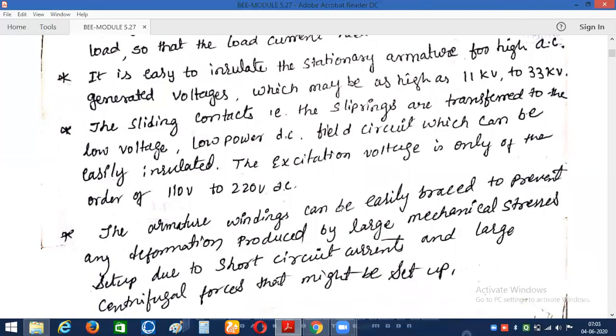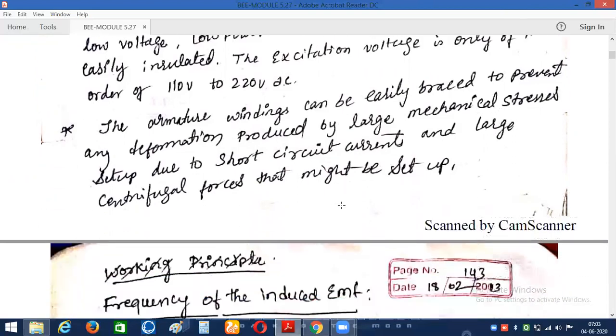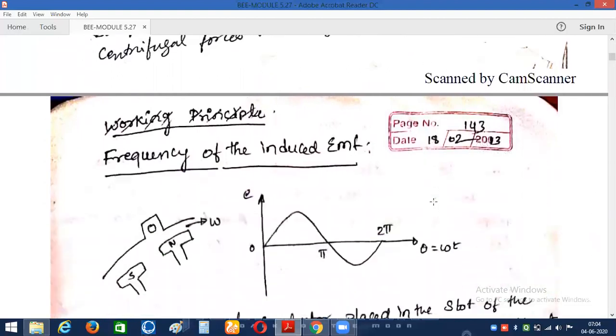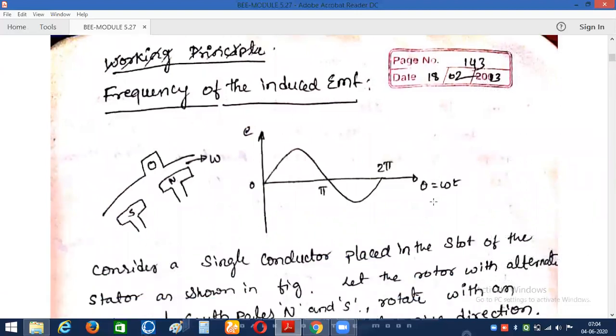The sliding contacts — that is, the slip rings — are transferred to the low-voltage, low-power side. This is also one more advantage. Additionally, the armature windings can be easily braced to prevent any deformation produced by large mechanical stresses set up due to short-circuit current and large centrifugal forces. Since the armature is stationary, the armature windings can be easily braced — whereas if it were rotating, it would be a tough task. Because of these advantages, we go for a stationary armature.